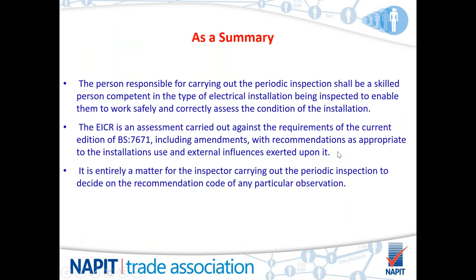So, as a summary, the person responsible for carrying out periodic inspection work shall be a skilled, competent person in the type of electrical installation being inspected. This will enable them to work safely and correctly assess the condition of an installation. Now, obviously, if your main field of work is in domestic work, you may not be comfortable carrying out a periodic inspection report on an industrial unit, and so on and so forth. So again, it is down to you to decide how comfortable you are in that line of work.